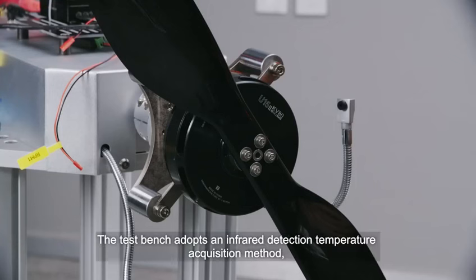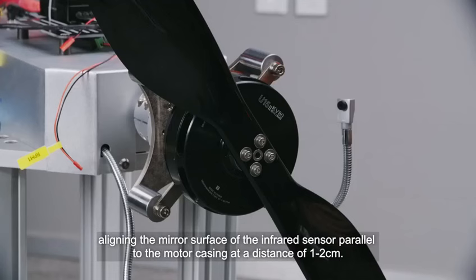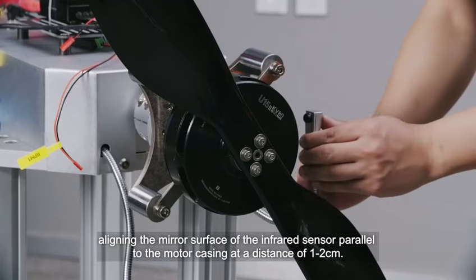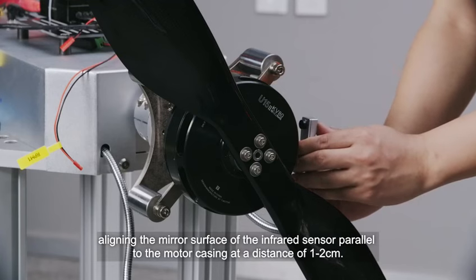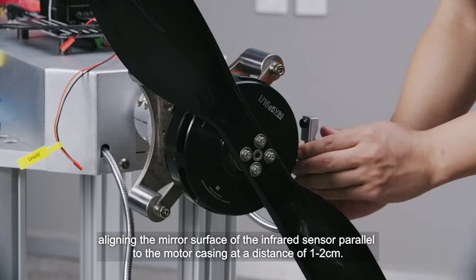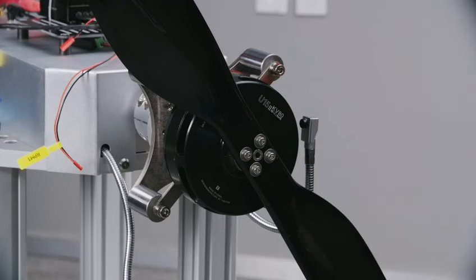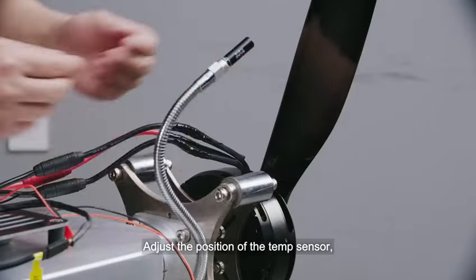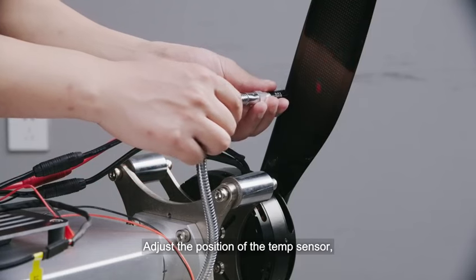The test bench adopts an infrared detection temperature acquisition method, aligning the mirror surface of the infrared sensor parallel to the motor casing at a distance of 1 to 2 cm. Pay attention to keeping the lens clean and avoiding oil stains blocking it. Adjust the position of the temp sensor.